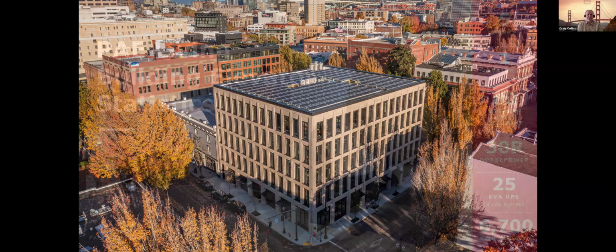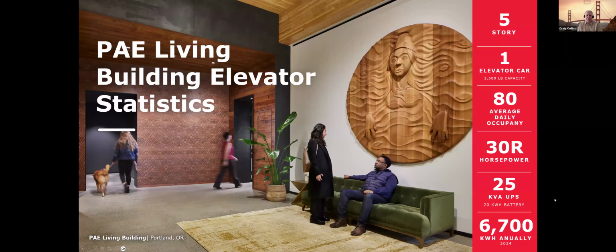Next slide, please. A little bit about the elevator in our building, and why we're talking about the PAE Living Building with respect to elevators: we actually have a UPS system in our building to drive our elevator. One of the key tenets of the Living Building Challenge, which is why it's called the PAE Living Building, is that we were not allowed to use any combustion technology within the project. Because we're a 5-story building, we were required by code to have an emergency backup source of power for our elevator, and we could not do a conventional diesel or natural gas generator, so we had to come up with an alternate solution that would provide the legally required standby without any combustion.